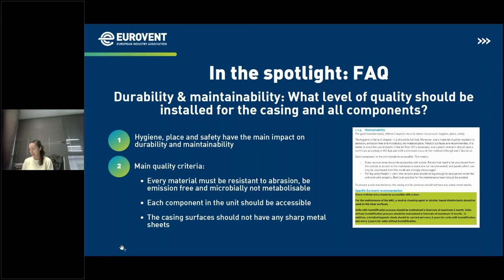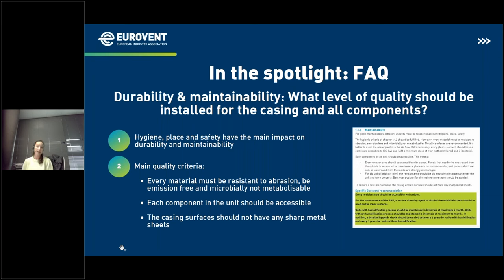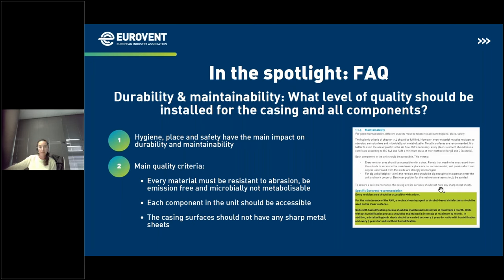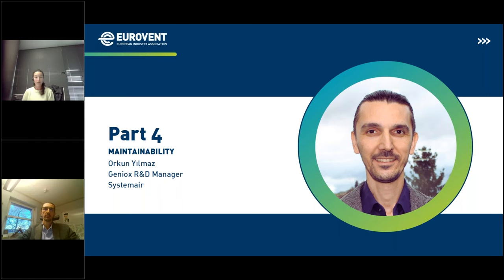This recommendation is also linked to other Eurovent recommendations — for example, on the optimal control of AHU operation. On durability and maintainability, we describe how hygiene, place, and safety can have an impact on the lifetime of the unit. The main quality criteria include, for example, resistance to abrasion for every surface in the unit — not only the casing, but also the components — accessibility for each component with a proper door and enough space in the unit, and no sharp metal sheets anywhere in the unit.